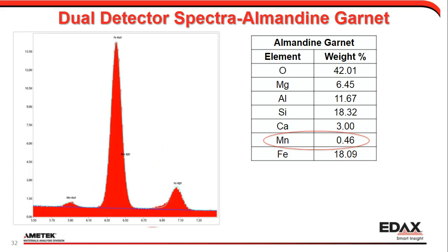So this really is a very small peak, very low counts we have in there. And for the observant viewer, you would also notice that something's missing in my standards. The values I showed in the beginning are not quite true. If we look at this iron K beta, you can see there's a tail on the left-hand side, so I'm quite confident there's some cobalt in my sample that's not accounted for.